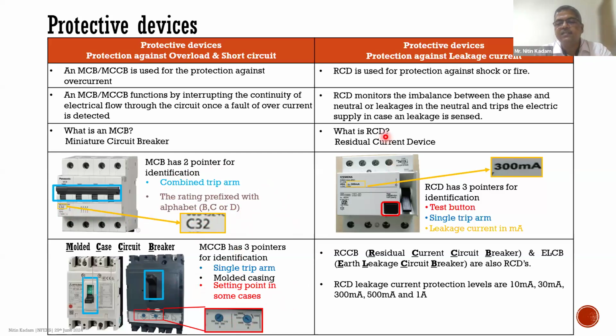In case of RCDs, they are basically used for detecting the leakage current, and the value of the leakage current is specified in milliamps. So you will have these values written down on the devices. In this case, it is 300 milliamps. You have a test button and you have a single trip arm.